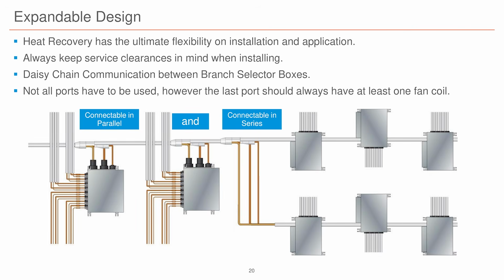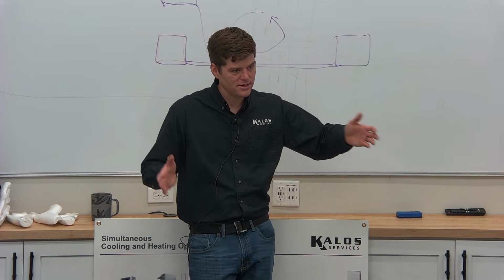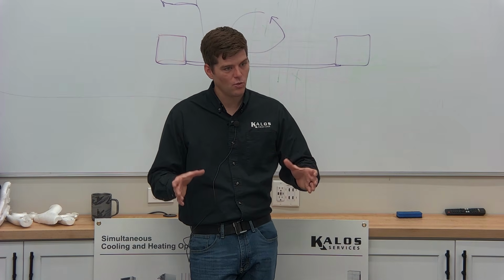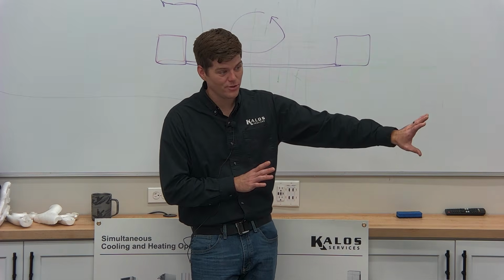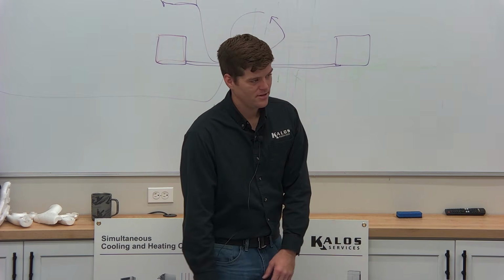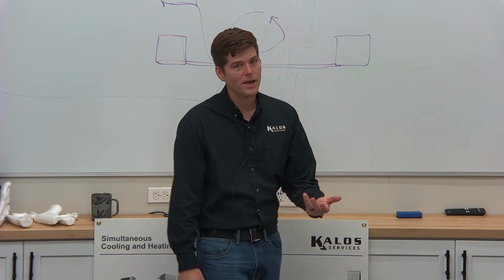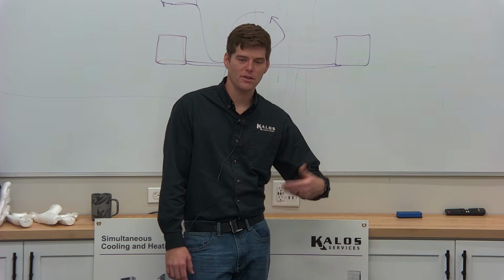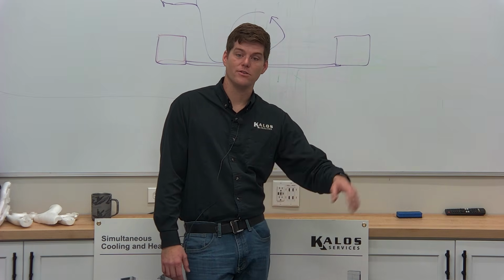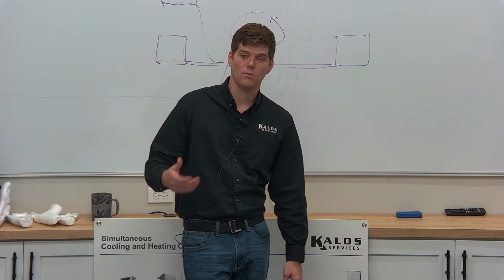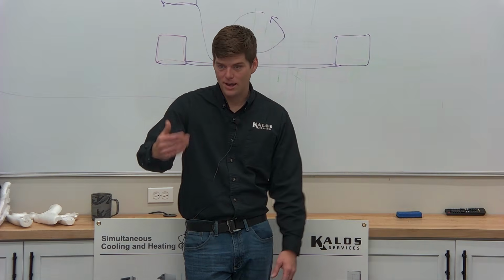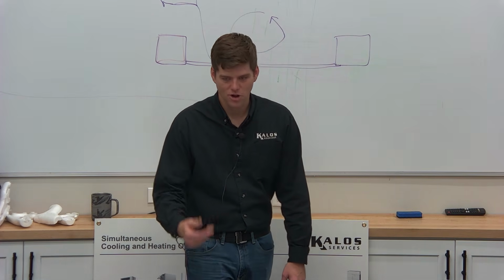Instead of having 15 outdoor units on the roof for 15 split systems inside, it's a nice, pretty little package on one stand and then 15 indoor units inside. And it's more efficient. Well, the reason this gets a bad rap is because they get installed very poorly by the cheapest bidder and they get a bunch of failures. And then you get contractors who don't know how to service them or work on them, and then it becomes, you know, a perpetual nightmare of just cost and cost and cost.